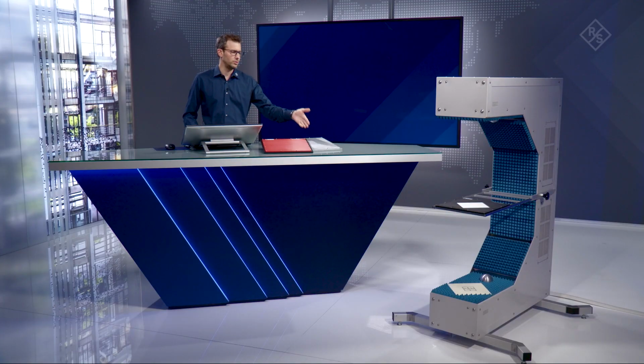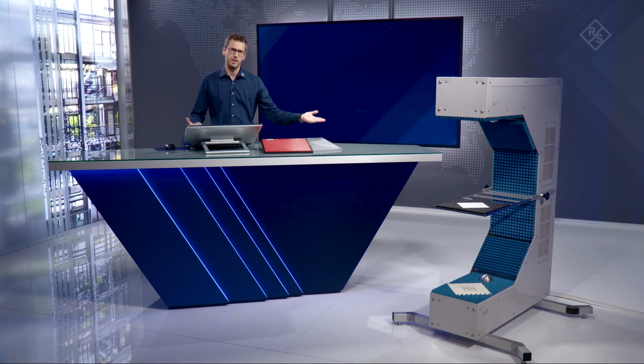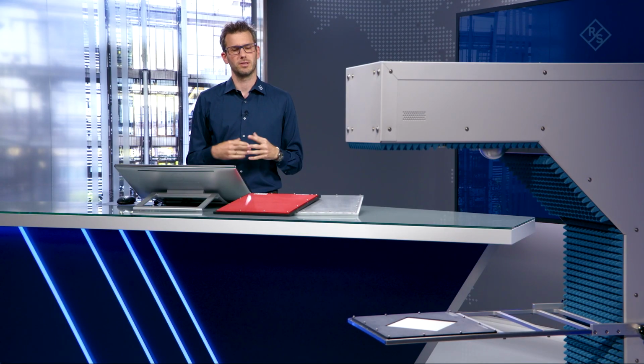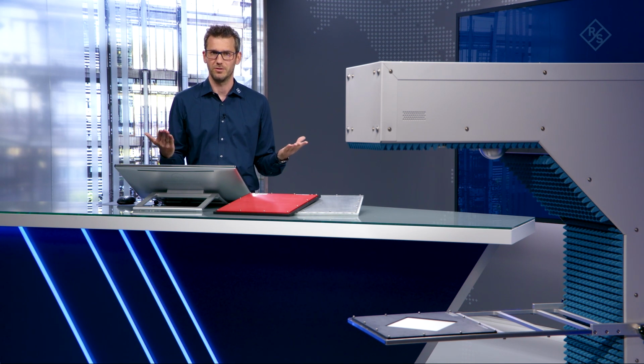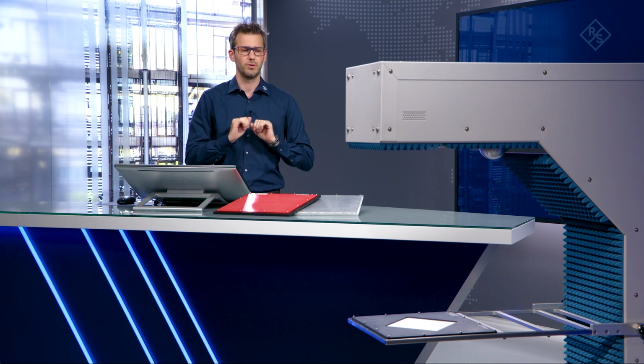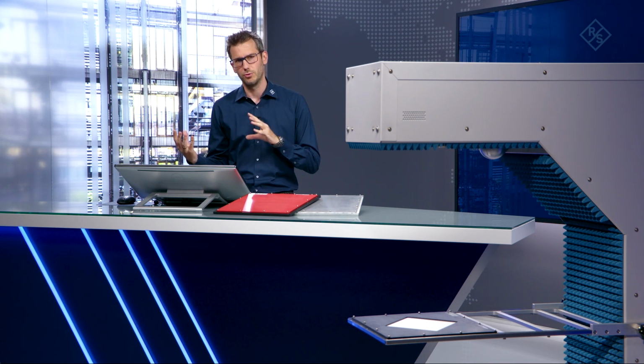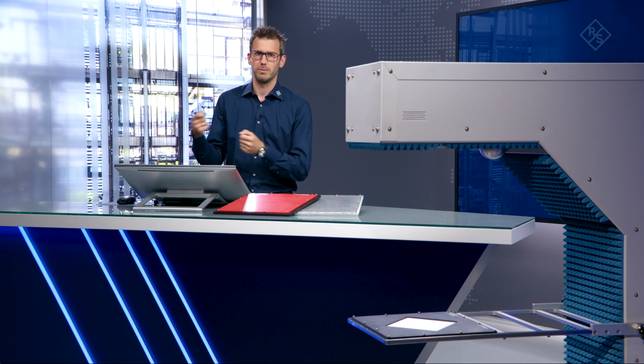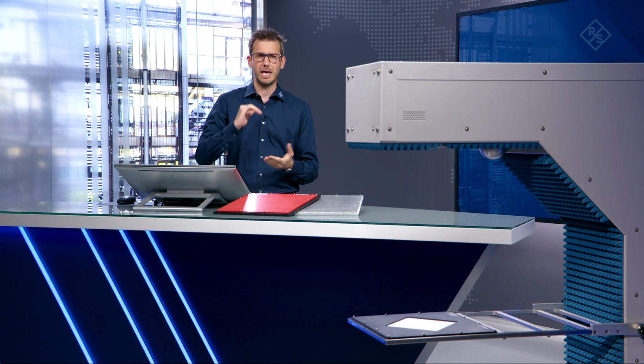a much easier life. So since calibration is not required very often, what is required a bit more often is the normalization. Therefore, normalization is a very simple process, and we are just using this metal plate that you can see over here. So basically, every metal plate does the job because the only thing it needs to do is be highly reflective. So metal usually reflects 100% of the signal. So that means we have our reference with 0 dB reflection. And in order to normalize 0 dB transmission, we just put the metal plate out and perform a through measurement with only air in between. So these are the two measurements we require for normalization.